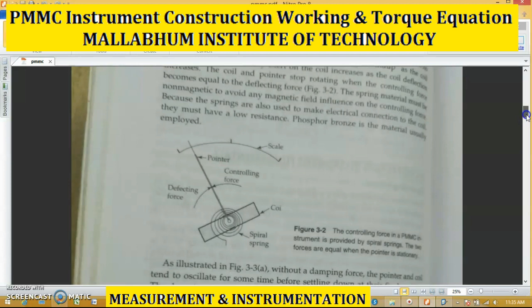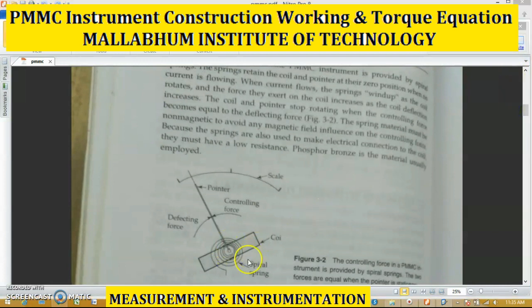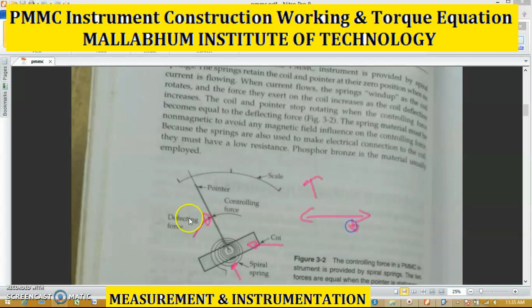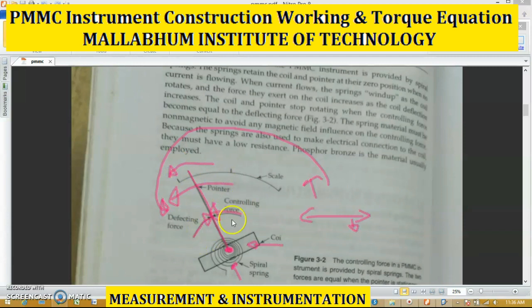This is the actual spring arrangement and this is the coil arrangement. The pointer is attached, and this is your deflecting force. This deflecting force is generated when current is supplied to the coil, flux is generated, and then a force is generated — that is the deflecting force. The controlling force: since the pointer is attached to the spring arrangement, the spring will try to move the pointer back to zero. The spring is responsible for returning the pointer to the zero position — that is your controlling force. Whenever these two forces are equal, the pointer rests at some point.